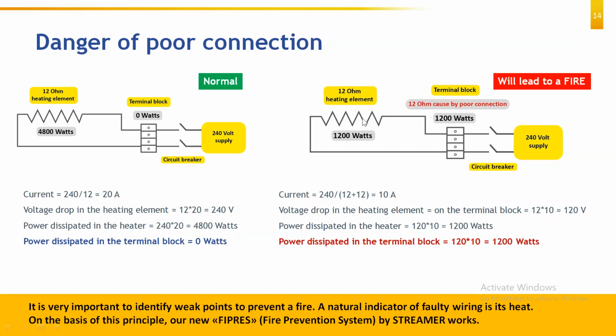Now the voltage drop at the heating element will be equal to the voltage drop on the terminal block, which will be equal to 12, which is the resistance, multiplied by the current flowing, 10, which will be around 120 volts. So there will be a 120 volt drop at the heating element and a 120 volt drop at the terminal block. The power dissipated in the heater will be equal to the power dissipated in the terminal block, which will be equal to 1200 watts.